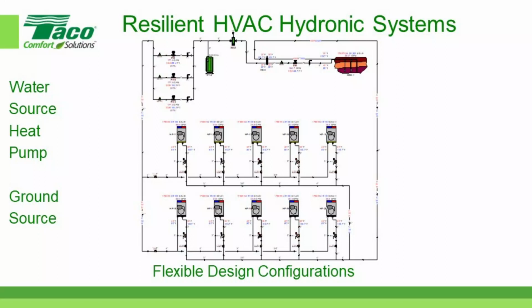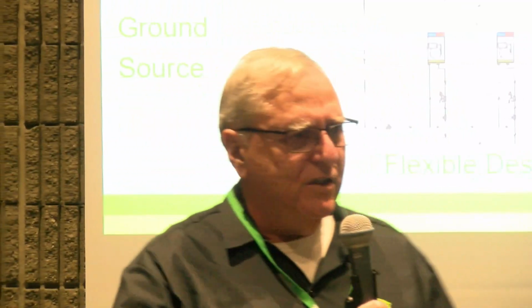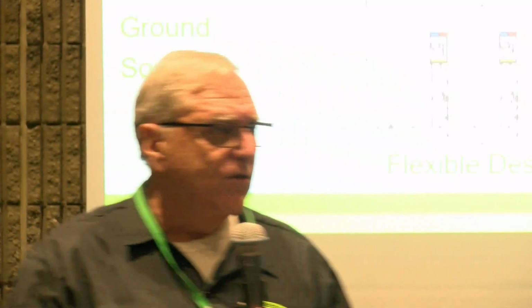It's using the ground at a constant temperature, 50 degrees, extracting heat from the ground and putting it into the heat pump, or rejecting heat back into the ground. So when you design a ground source heat pump system, you have to have equilibrium between summer and winter. The amount of heat you extract has to be roughly equal to the amount you reject.